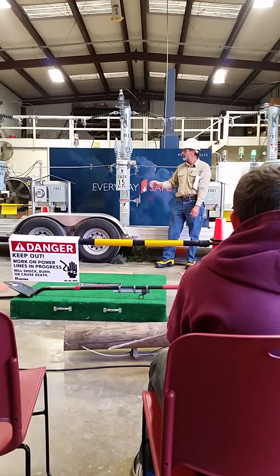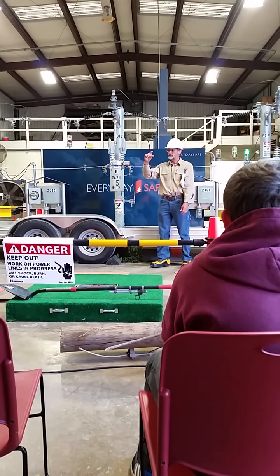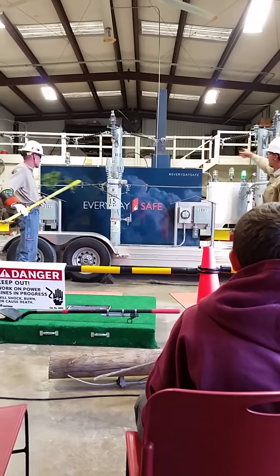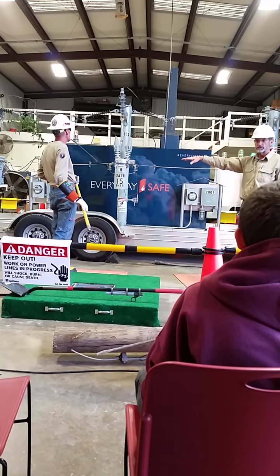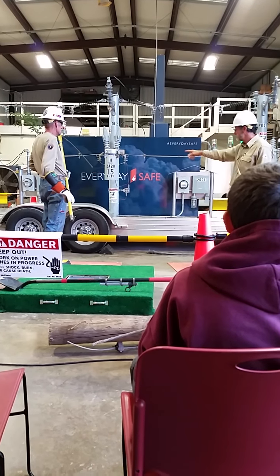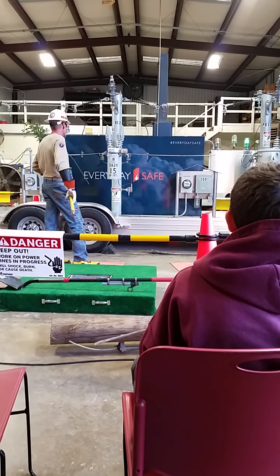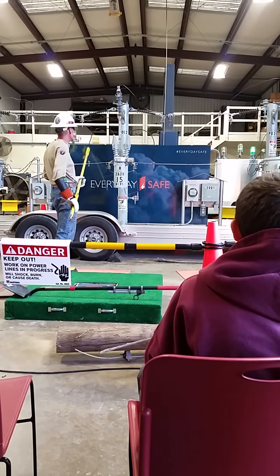It was a mechanical piece of equipment. So again, that line, never consider it dead. Even if that breaker is locked out, there's a set of contacts that are about that far apart in there in mineral oil. Randy's going to make the line hot for this cutout of this switch. And he's going to bridge that gap with this limb and show you that the light bulbs, this is 2001 Highway 69, these represent houses, and 2002 Highway 69. He's going to show you that he can energize those 2 transformers on the other end of the line with the green limb. So when you're ready, Steve.